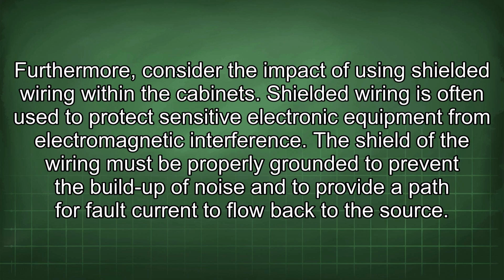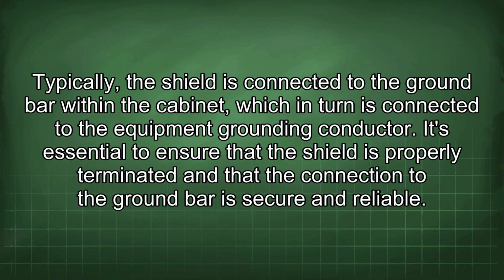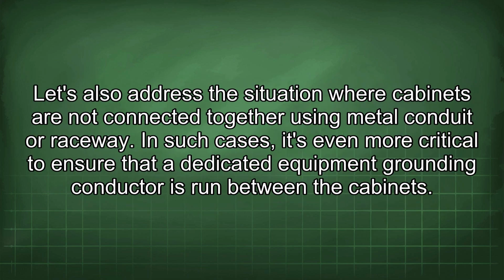Shielded wiring is often used to protect sensitive electronic equipment from electromagnetic interference. The shield of the wiring must be properly grounded to prevent the build-up of noise and to provide a path for fault current to flow back to the source. Typically, the shield is connected to the ground bar within the cabinet, which in turn is connected to the equipment grounding conductor. It's essential to ensure that the shield is properly terminated and that the connection to the ground bar is secure and reliable. Let's also address the situation where cabinets are not connected together using metal conduit or raceway.